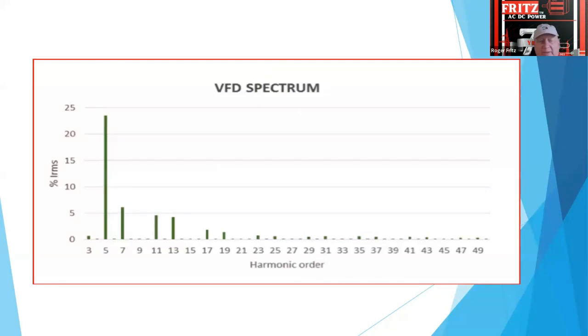So the reason I like to bring that up is that he's exactly right: if you have imbalances in voltages, or noise issues in the plant, they're just not picked up by your normal volt and amp meters. They're not quick enough responding, they can't see it. And this shows what they call the harmonic order, which is basically the frequencies at which distortion is happening.